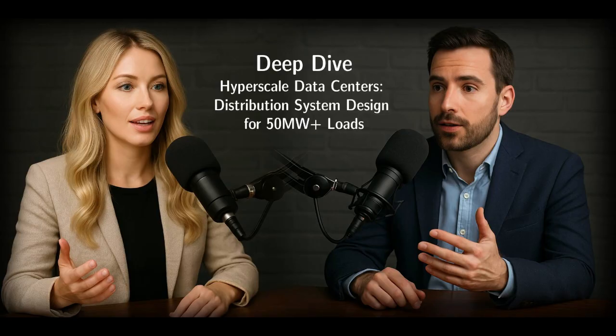And the engineering advantages must be pretty significant at that level. Oh, huge. First, you get transmission level reliability. That includes the ability to design for N-1 contingency. Meaning the system can lose one major piece, a line, a transformer, and keep running. Exactly. That's standard practice in transmission. Much harder to achieve reliably at lower distribution voltages for these load sizes. It often means you only need a single 69 kilovolt circuit instead of that mess of parallel feeders we talked about. Simpler configuration. Much simpler physically. You also get vastly better voltage stability and power quality over longer distances, and accommodating future load growth becomes much, much easier.